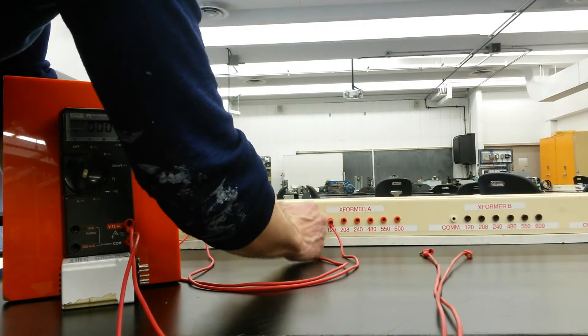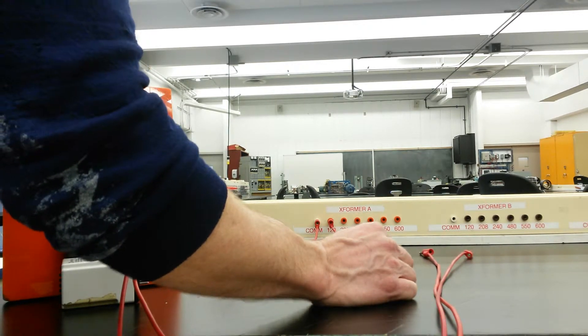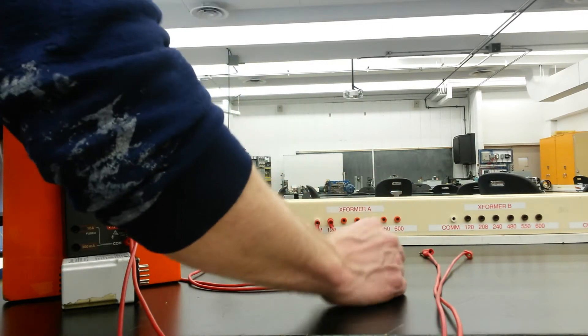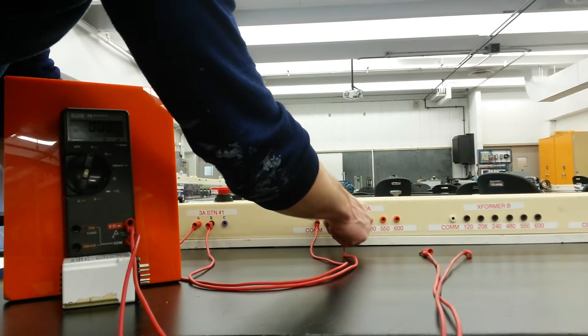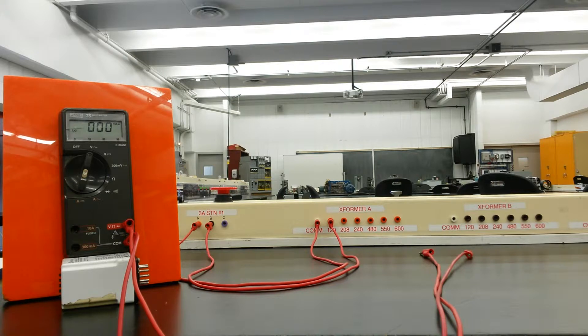You've now upped the voltage per turn, so volts per turn ratio for the entire transformer. So now between the common and the 600 volt turn, you'll see that ratio of increase between 208 and 120, which we know is 1.732 or root 3.